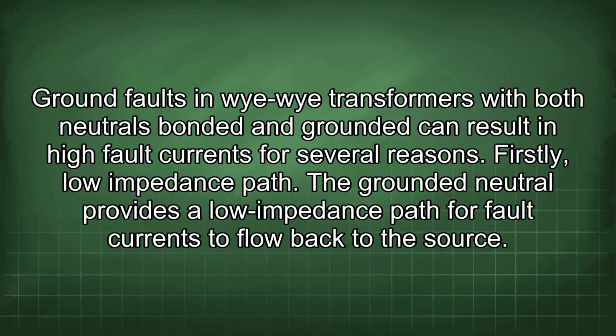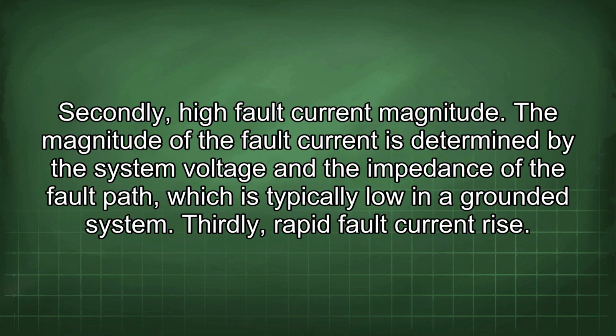Ground faults in Wye-Wye transformers with both neutrals bonded and grounded can result in high fault currents for several reasons. Firstly, low impedance path. The grounded neutral provides a low impedance path for fault currents to flow back to the source. Secondly, high fault current magnitude. The magnitude of the fault current is determined by the system voltage and the impedance of the fault path, which is typically low in a grounded system.